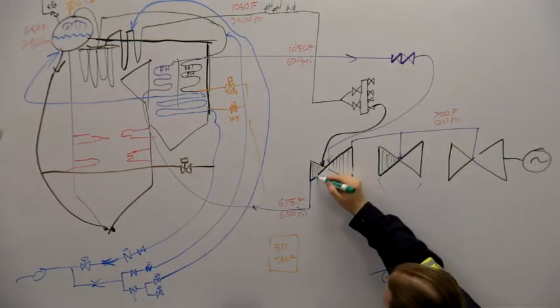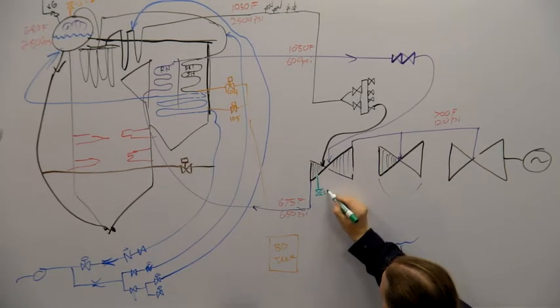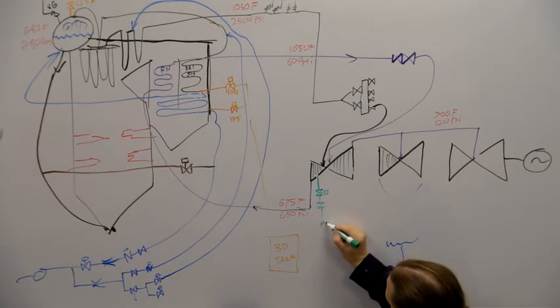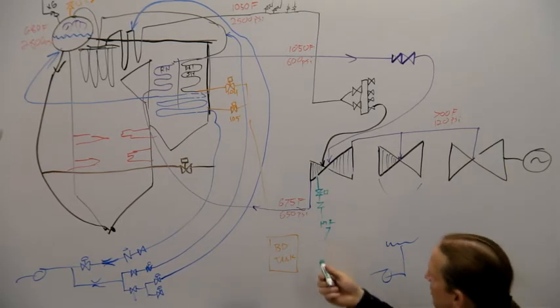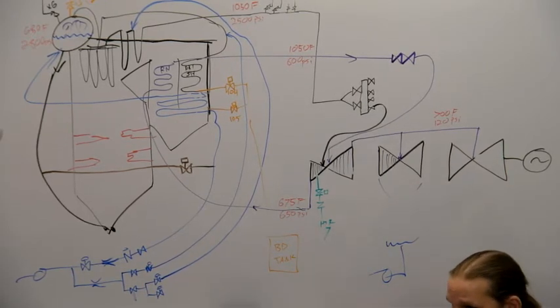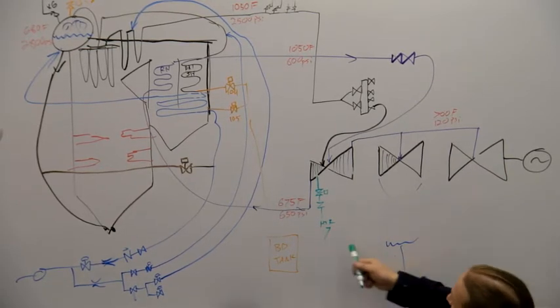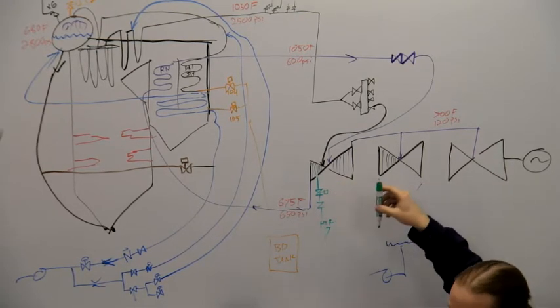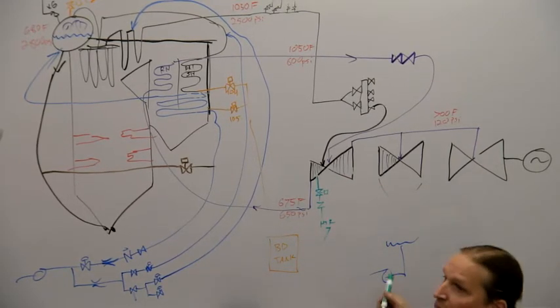So we scoop off in a whole bunch of different places. And they each have a motor operated valve and a check valve. And then that goes to heater 7. The heaters are numbered where the lowest is the coolest, the first one you hit. And they're numbered up, 1, 2, 3, 4, 5, 6, 7. I'm talking about them kind of in the opposite direction because I'm going from higher pressure to lowest pressure. Highest energy steam to lowest energy steam. So heater 7 and then coming off of the cold reheat, we're going to heater 6.